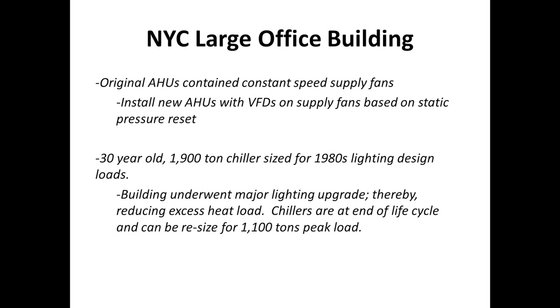This building also had a 30-year-old 1,900-ton chiller, sized for 1980s lighting design loads. Essentially, this building has undergone many renovations on the lighting side. In the 1980s, it was all T12 bulbs with magnetic ballasts. They give off a lot of heat to the space. Since then, a lot of the lighting has been replaced with T8 and T5 bulbs, and compact fluorescents instead of incandescent, which really reduced the cooling load substantially.